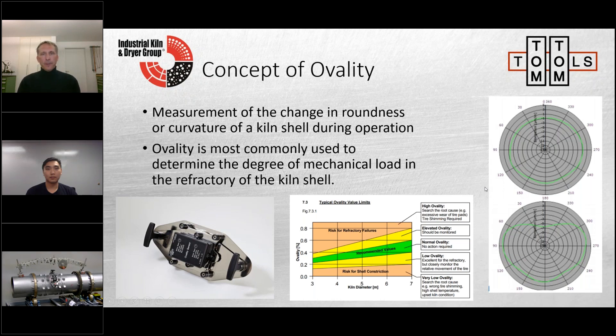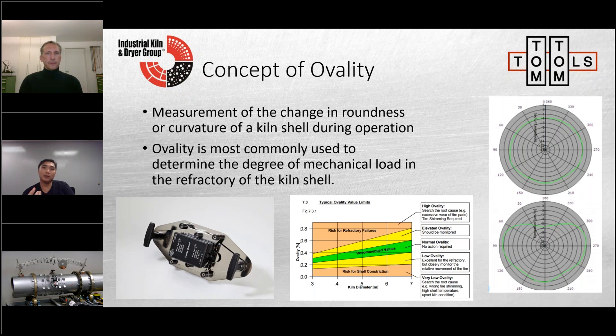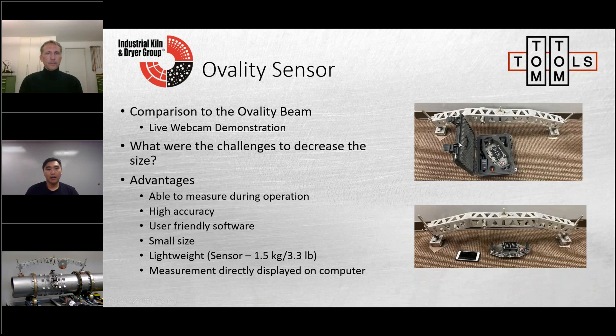We've also done work outside of normal ovality measurement — using the sensor on stiffener rings for dryers and seeing major deformations due to stress at those particular spots. Because the ovality sensor uses strain gauges, it's useful for understanding shell deformation even outside of normal kiln tire ovality applications.